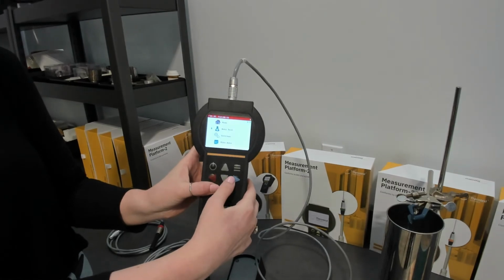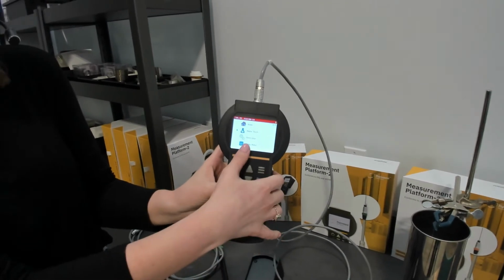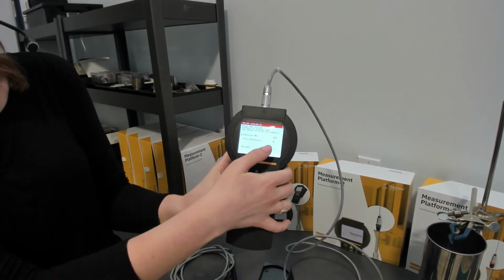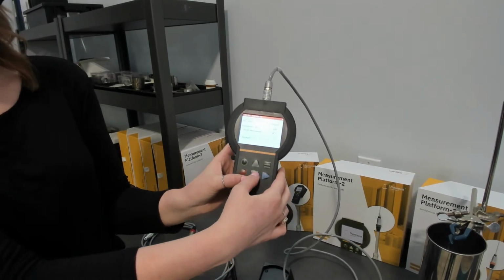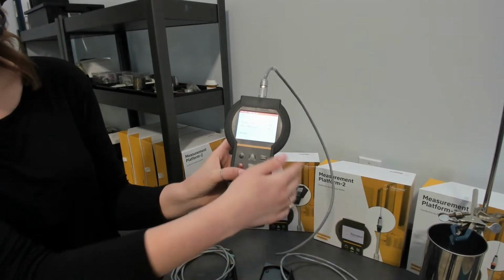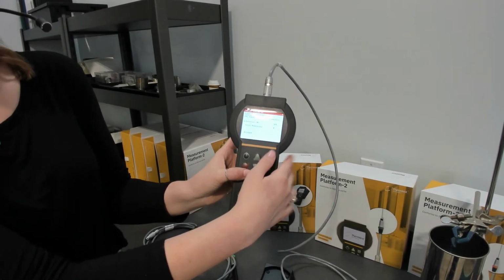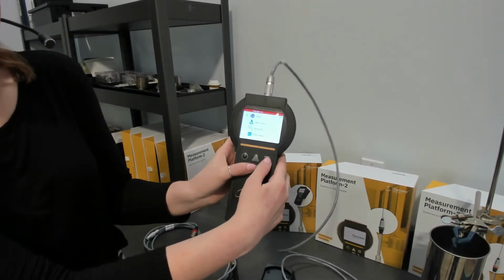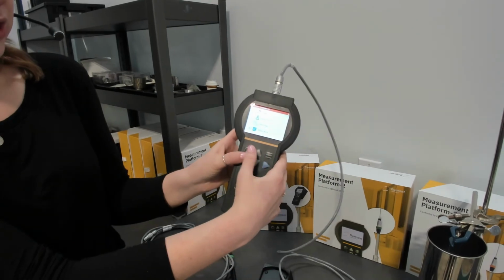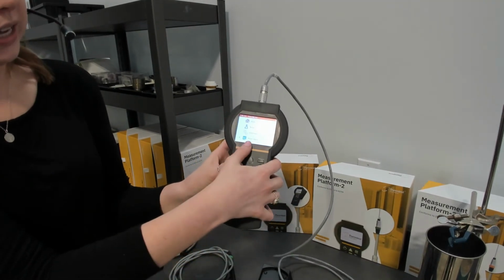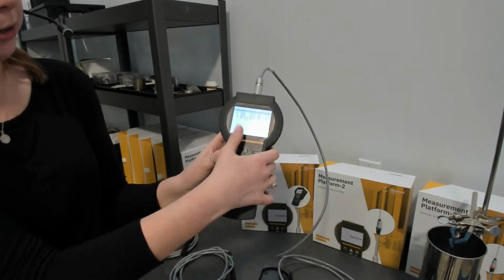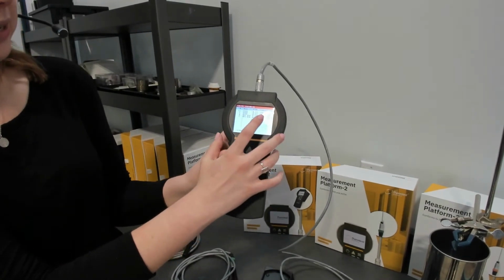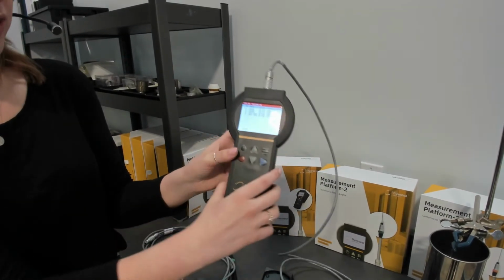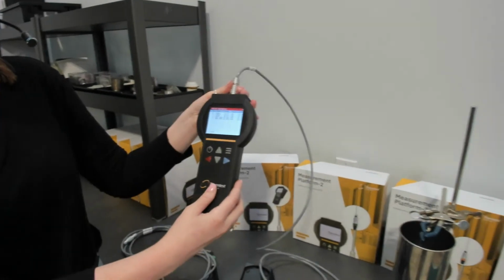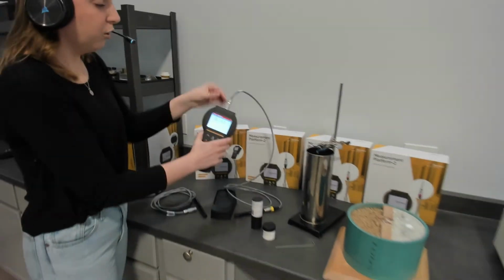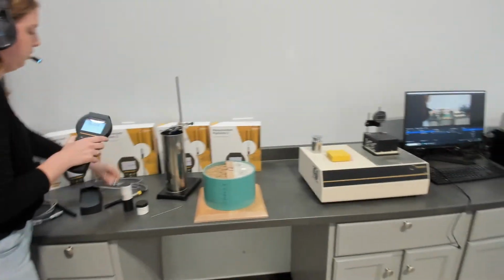If you want to set up a series of automated tests, you can go to the auto test function and select the interval of time between tests and the number of tests you'd like to perform and accept. This will begin an automated schedule of measurements, so you could just leave and let these run on their own. Once we're finished running tests, you could go to the view data function to review some of your tests. This has limited view of all the results, so we can take this to the software for further analysis. So we're just going to remove our sensor and move to the software.